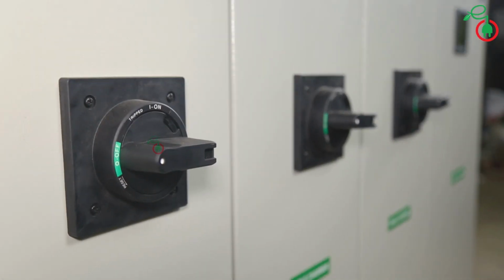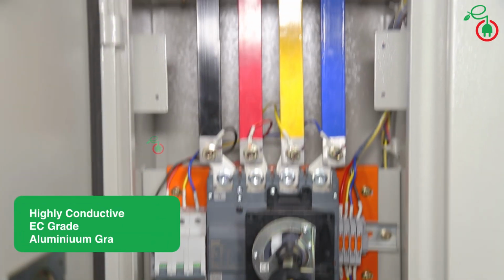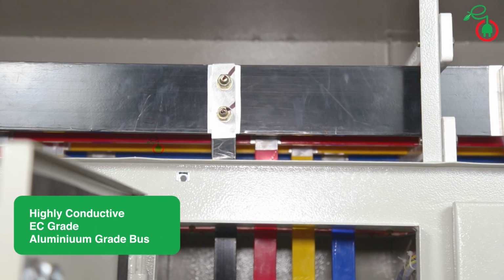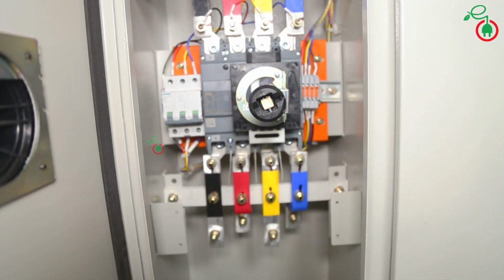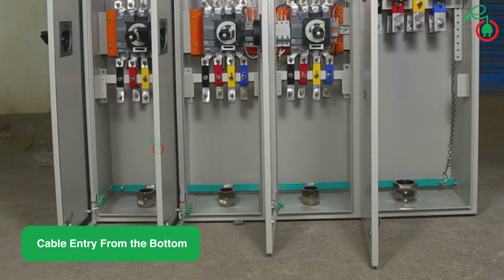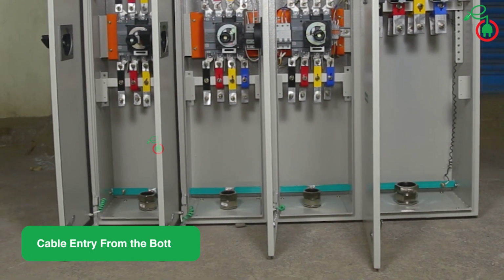We have used Schneider make MCCBs. The complete panel is constructed with EC grade aluminium busbar. The output cable is taken from a busbar. That cable will be connected to a customer main LT panel. Here all the cable entries of input and output are from the bottom.